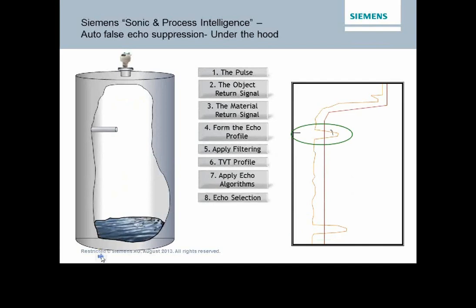We then make a selection based on a number of factors in terms of area, largest and first. What echo we use will vary based on the tank itself. We can actually take a look at false echo suppression, and those things that we see in the tank that we know are going to be there, we put into memory in the unit. So it'll compare all future echo profiles to that original echo.